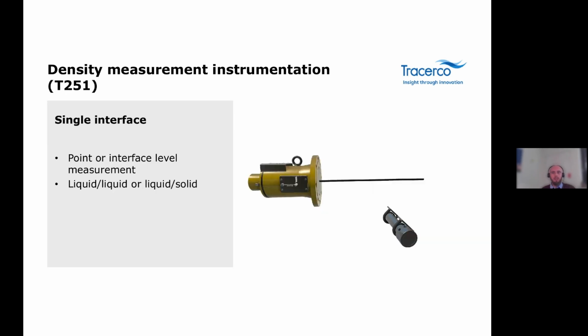In some applications, the source can be used inside a dip pipe. This is still a non-contact solution and can provide accurate interface trips or interface level measurement. It can be used for both liquid-liquid and liquid-solid interfaces, such as sand or build-up accumulation.